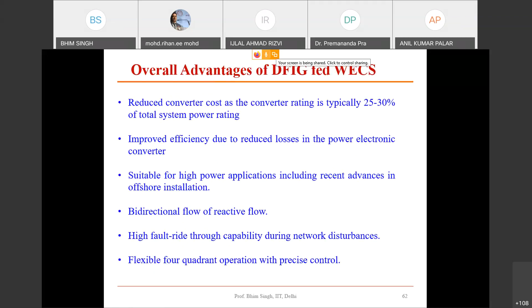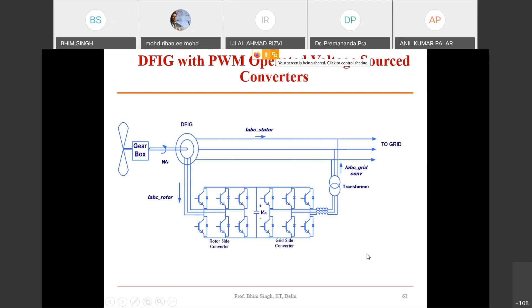So that's about the control. Of course, I can tell you it is the same thing which I already talked about. You use the voltage source converter. The DC link voltage is regulated by this converter because you may need to feed power in this manner if the rotor speed is high, and if the rotor speed is low, then you have to feed power from this side. So this converter will need power, according to the slip power recovery principle, the same principle is applicable here. But as far as control is concerned, you have to regulate the DC link voltage, regulate the stator power factor to unity by adjusting the reactive power, and put MPPT also. So typically you require current control also. In our benchmark system, my students and I use typically 8 PI controllers in this system. So that's the basic principle I already talked about.